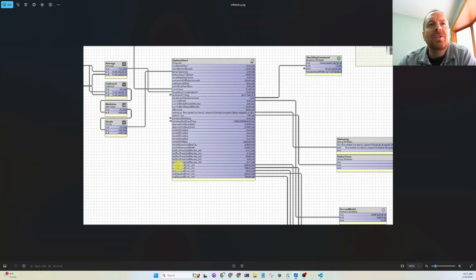So what I'm trying to do is also track squared error and averaged squared error. So over time, there's another parameter in here called the auto mode. So after 3 days, we'll start actually controlling to the model that has the best squared error over time, average squared error over time. And as you can see in here, we're predicting where model 2 actually has the best average squared error.